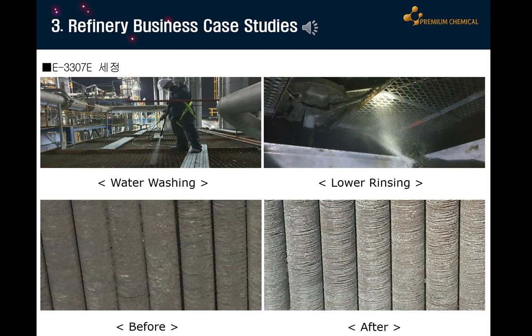Looking at the before and after images below, the aluminum fins are coated with foreign matter, making them undetectable to the naked eye. The gaps between the fins are completely blocked. However, after chemical cleaning, the fins are clearly visible, revealing the excellent quality of the chemical cleaning. Considering the difficulty of removing dust, oil particles, rust, and other debris from the aluminum fins without damaging them, these results clearly demonstrate the premium value of premium chemicals.